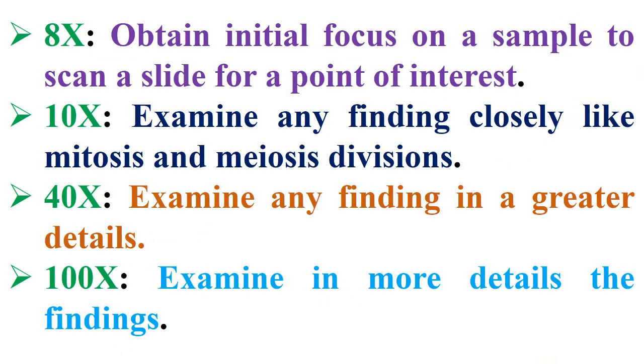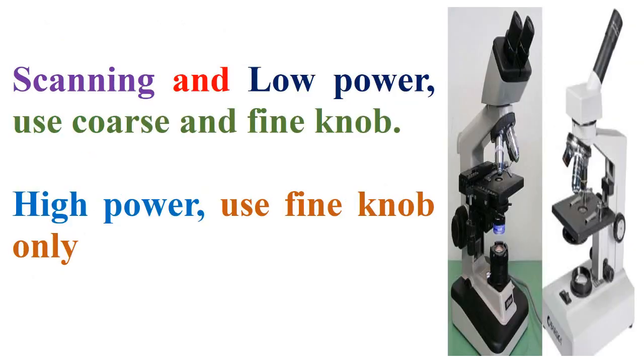Therefore, 8x is used to obtain initial focus on a sample and to scan a slide for a point of interest. Meanwhile, 10x is used to examine any finding closely, like mitosis and meiosis divisions. Whereas 40x is used to examine any finding in greater detail. In addition, 100x is used to examine findings in more detail. For scanning and low power, use coarse and fine knobs; for high power, use only the fine knob.